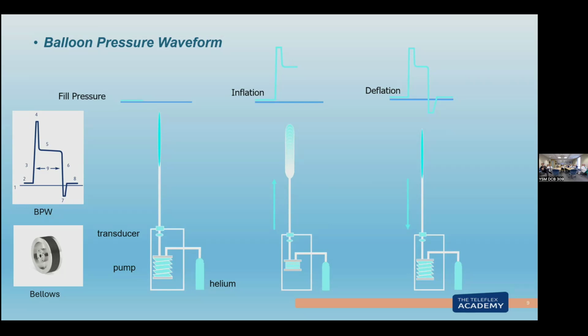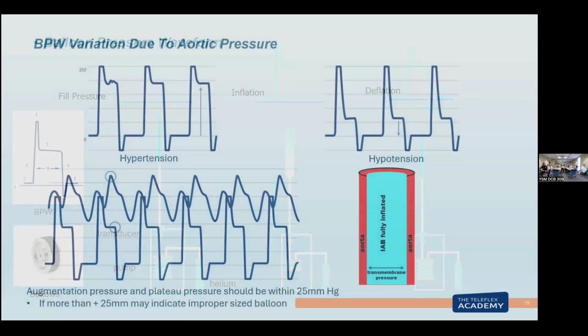Then when it's ready to inflate, so we're up on R wave, I've got my helium ready, the bellows pushes that volume to the balloon, goes straight out, goes past the transducer, plateaus out, and then the bellows pulls it back out when we're ready to deflate. So this is why we're different from a vacuum compressor. We are a motor driven bellows system. This is a stainless steel bellows. This never wears out. This is pretty much the same design they've used since the beginning, back in the 60s, 70s, when we started all of this.